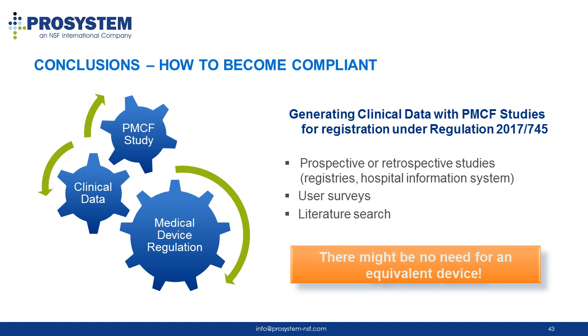If you have previously used clinical data from an equivalent device which no longer fulfills the regulation requirements of equivalence, or if your device has been on the market for a long time, but there are not enough clinical data available, or for other reasons you have determined that further clinical data is required for the registration of your device under the regulation, you might consider collecting clinical data now, during the transition period, with your current CE marked device.